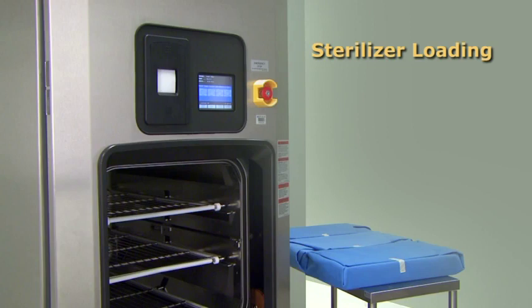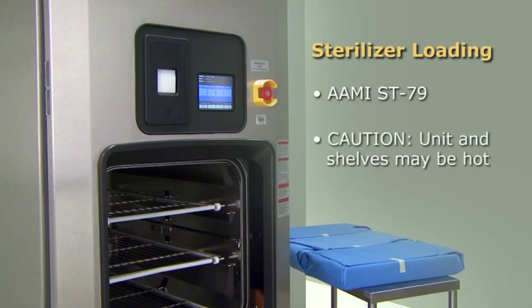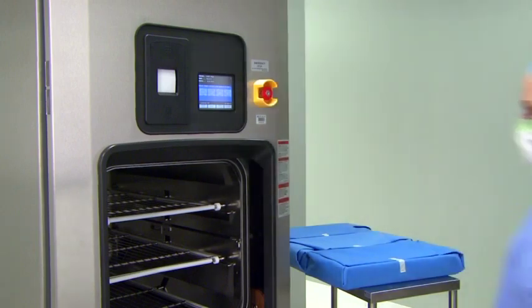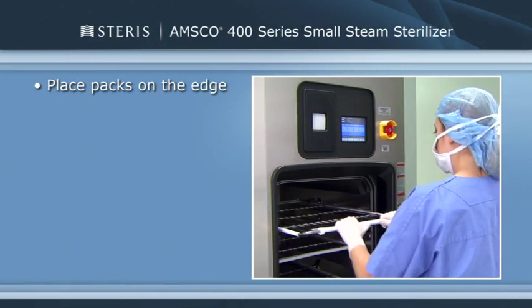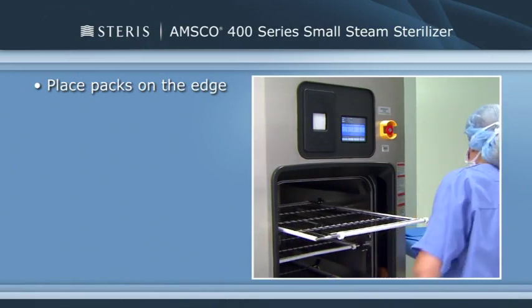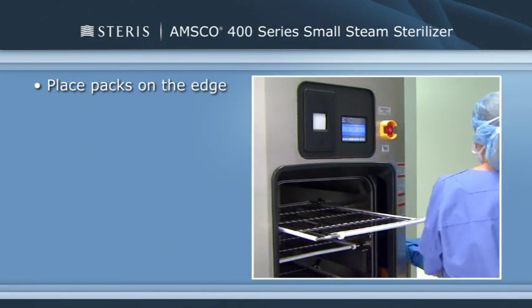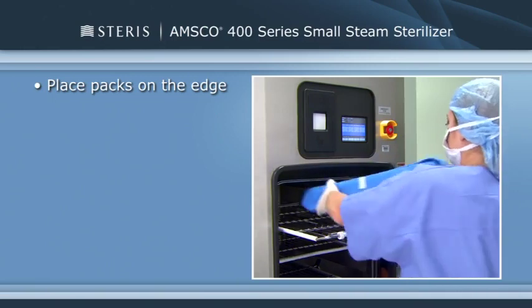Next comes placing the loads in the unit. Specific guidelines can be found in AAMI ST79. If a cycle has been run, the unit and shelves may be hot. Wear clean gloves or mitts and use clean towels as pot holders when loading. Place all packs on the edge and arrange the load to allow for maximum steam exposure so there is minimal resistance for steam passage through the load.